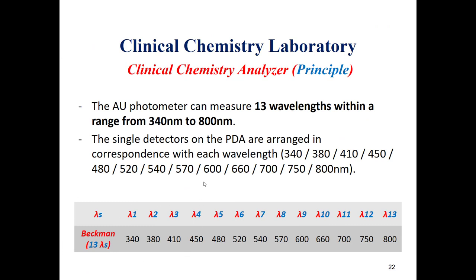The photometer used by Beckman has 13 wavelengths ranging from 340 nanometers to 800 nanometers. These are the 13 wavelengths used by Beckman analyzers.